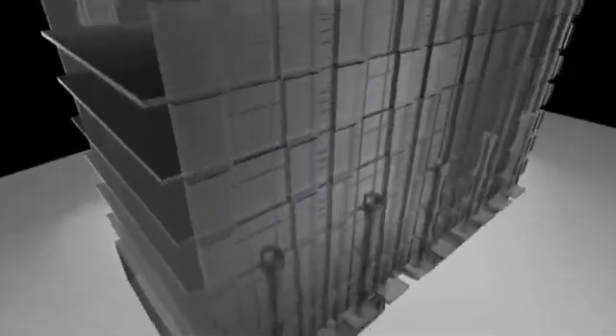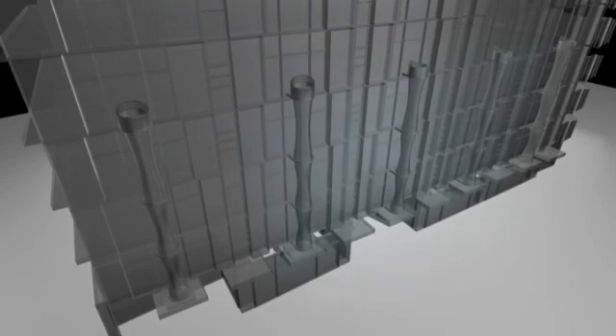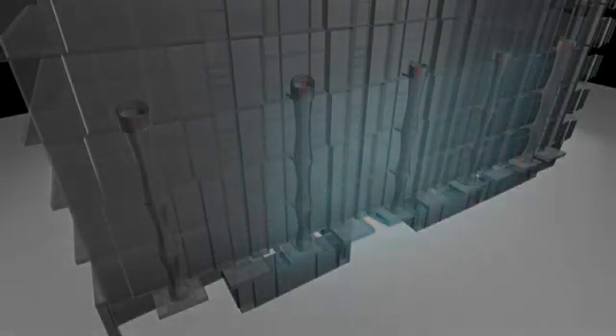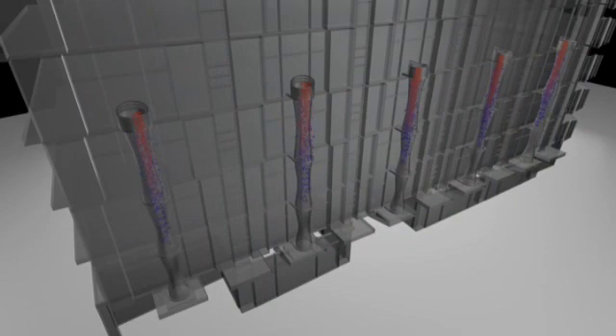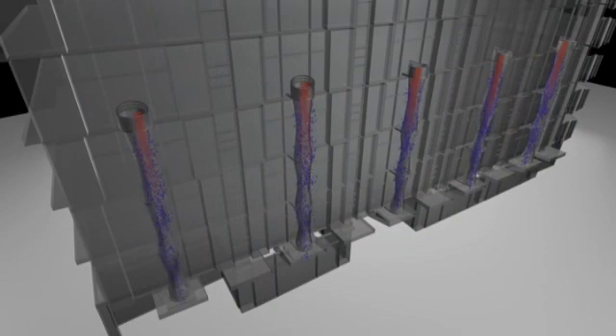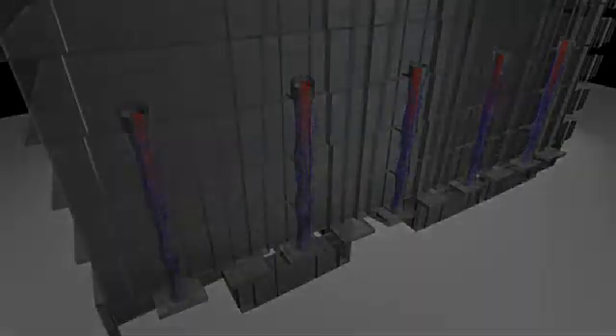These shower towers use evaporative cooling to cool down air and water. Water is cooled by being dropped 15 metres through the towers, and as air falls with it, it is cooled by evaporation from the shower of water. The air is then used to cool the retail spaces on the ground floor.